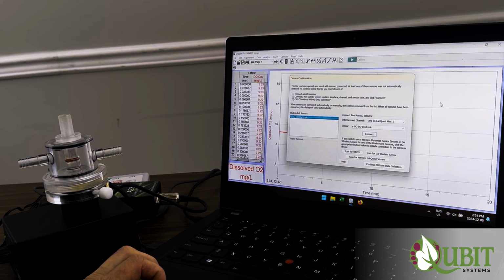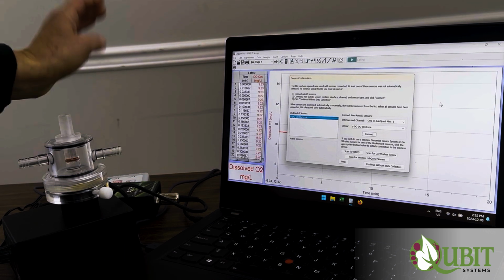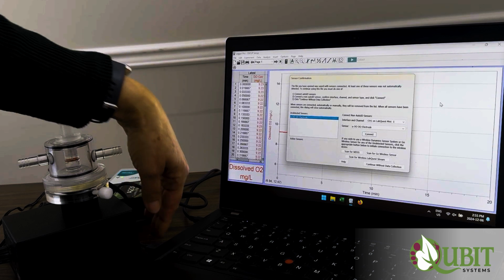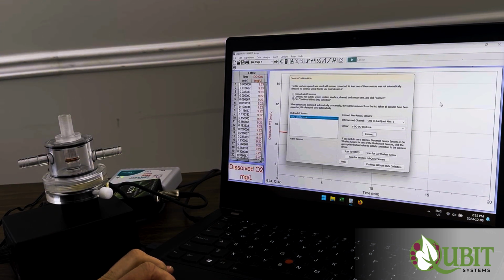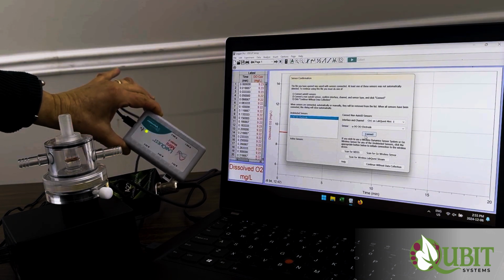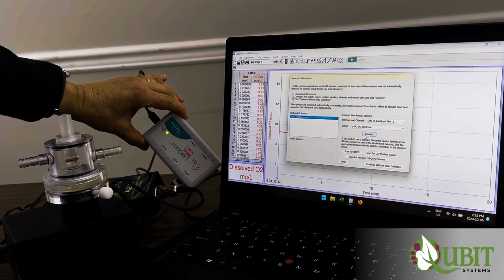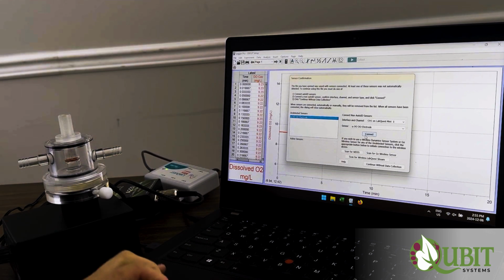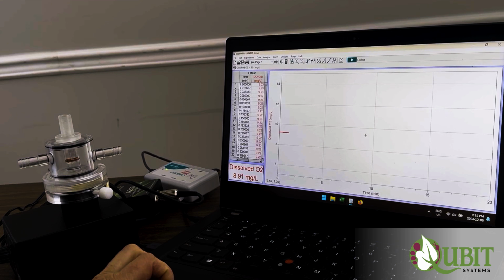This experimental file can be copied to your computer, and once your LabQuest Mini is connected to the USB port of your computer, which you've done earlier because you've been polarizing the electrode, when you open that experimental file, you will be shown this sensor configuration window, where you have to select the DO electrode as your sensor on channel 1 of LabQuest Mini 1, which is where we have it connected. There are 3 channels on your LabQuest Mini, and the oxygen electrode is connected to channel 1. So you click connect, and now your electrode is recognized.